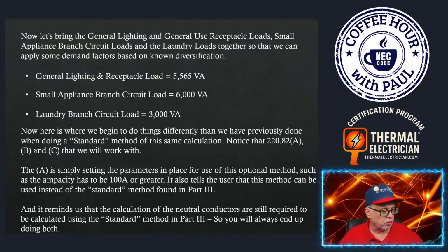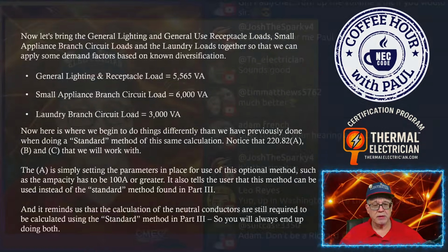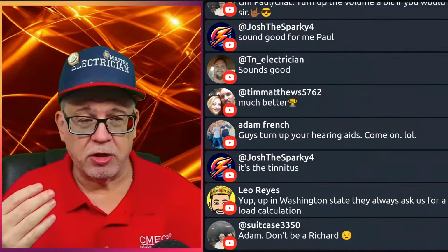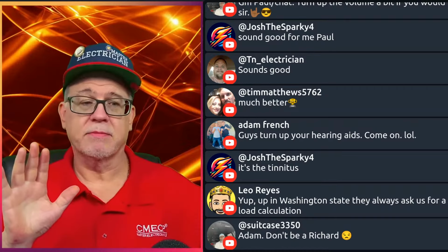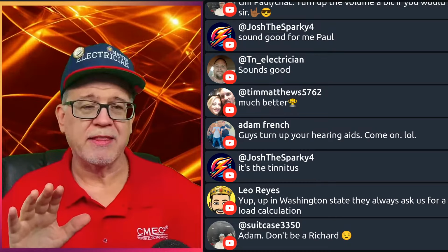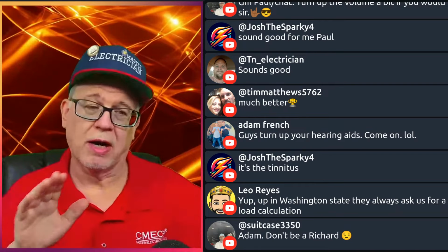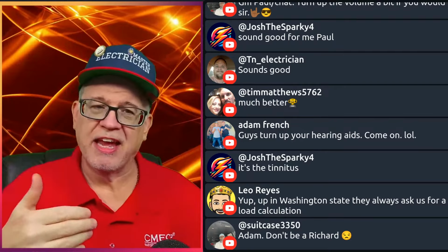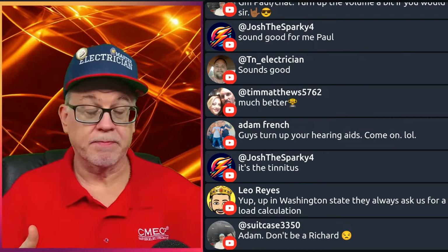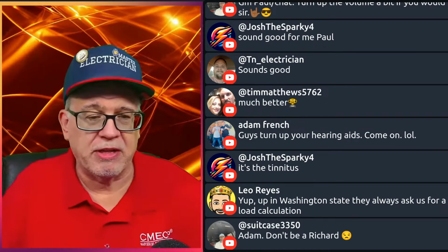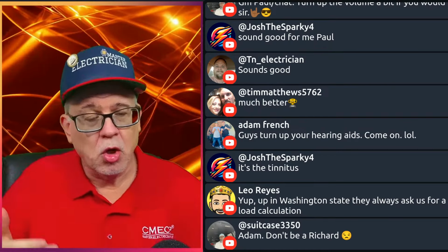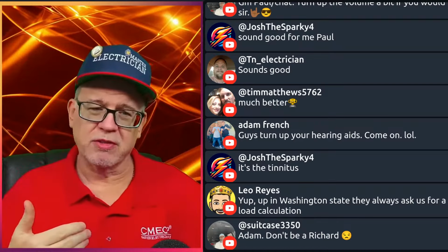If your neutral is 2/0 and your hots are 4/0 aluminum, you're going to be okay. There is absolutely nothing in that dwelling, neutral-wise, that should cause it to come anywhere near the 2/0. That's just a safe, easy way to apply it in the field. Now, if you buy the cable assembly, it's already made. As manufacturers, we can't make the neutral conductor more than 2 sizes smaller, so it just saves you a little time.